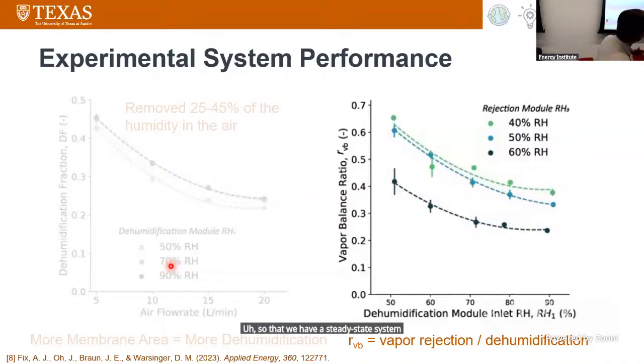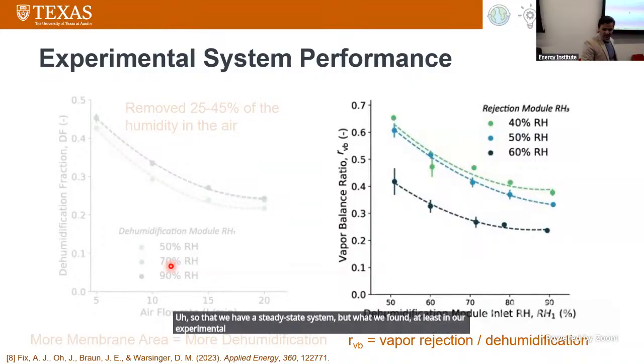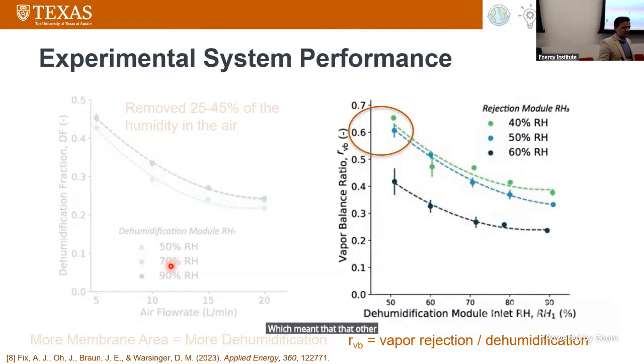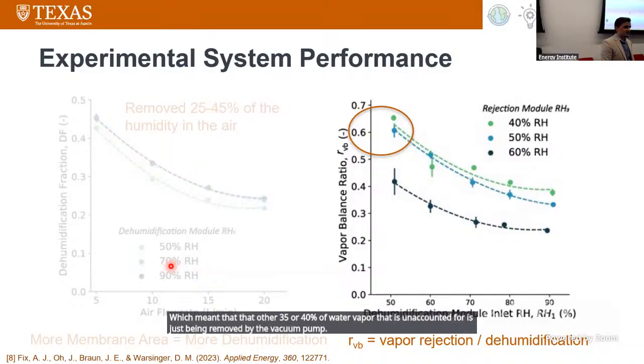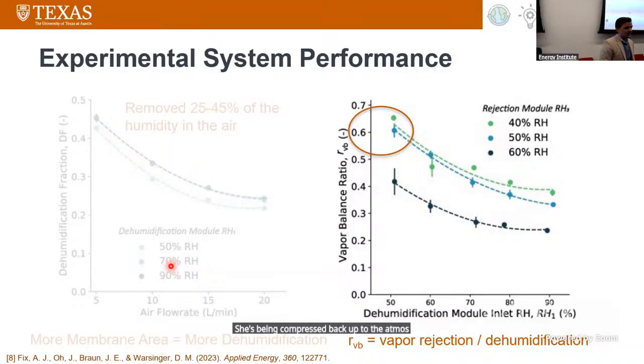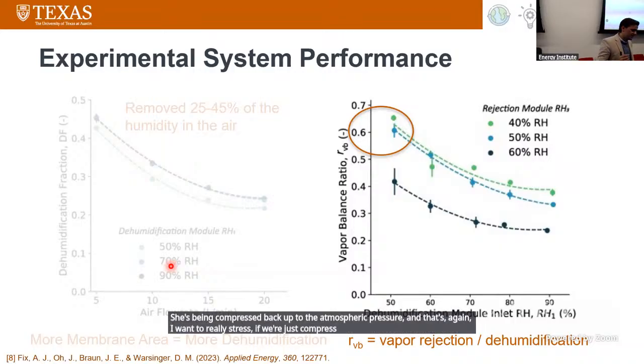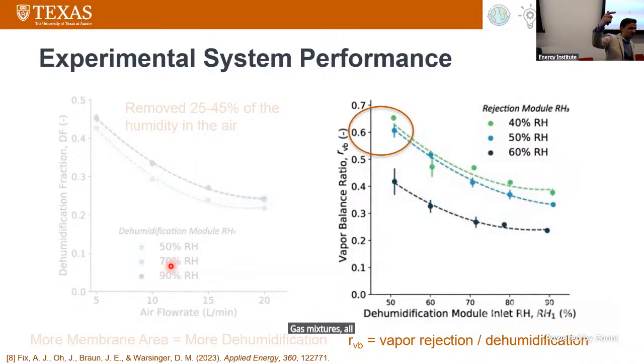But what we found, at least in our experimental prototype, was we were maxing out our system more around 60 to 65%, which meant that other 35 or 40% of water vapor that is unaccounted for is just being removed by the vacuum pump, just being compressed back up to atmospheric pressure. And I want to really stress, if we're just compressing gas mixtures all the way back up to atmospheric pressures from vacuum, that's inefficient. That takes a lot of energy.